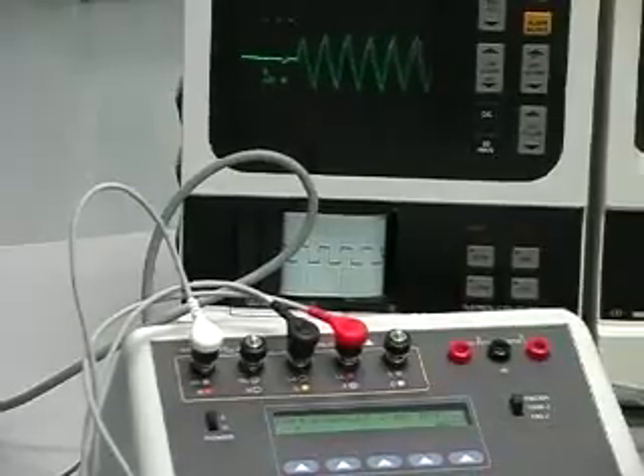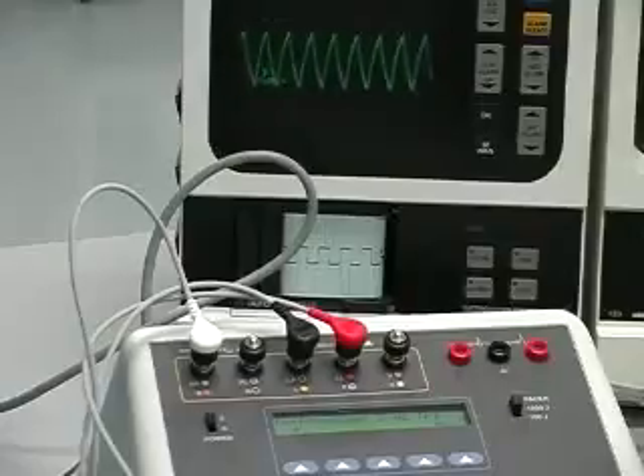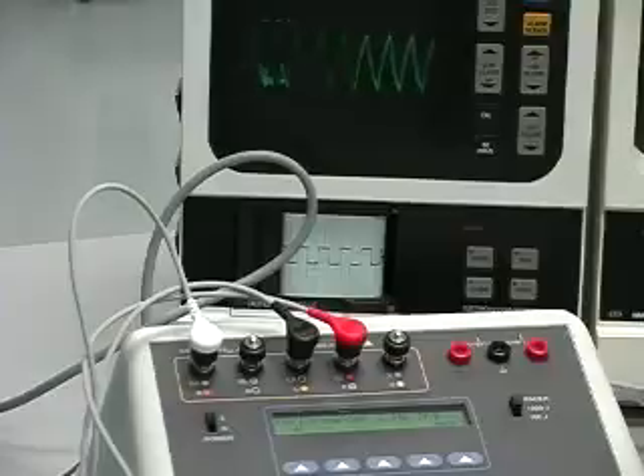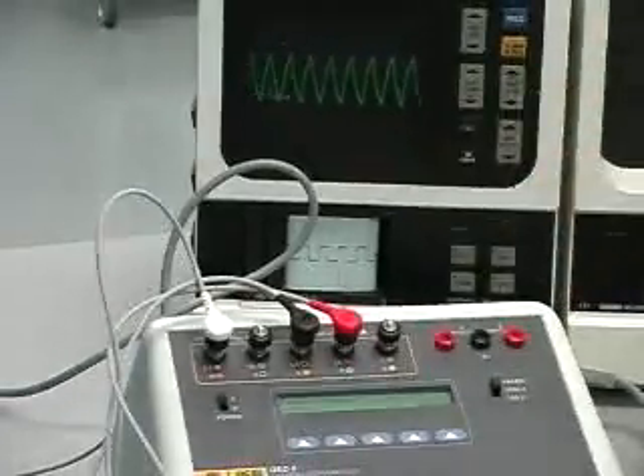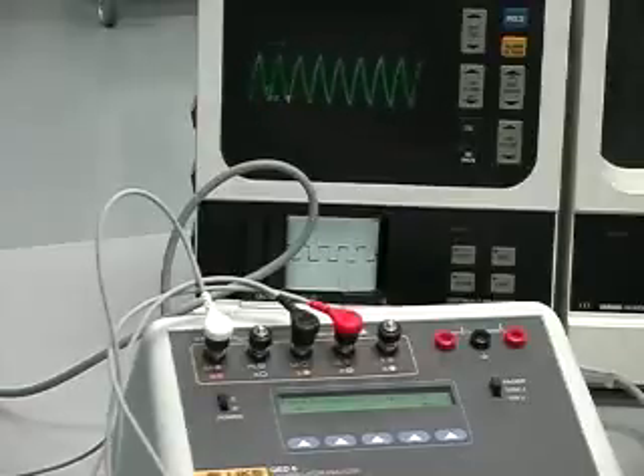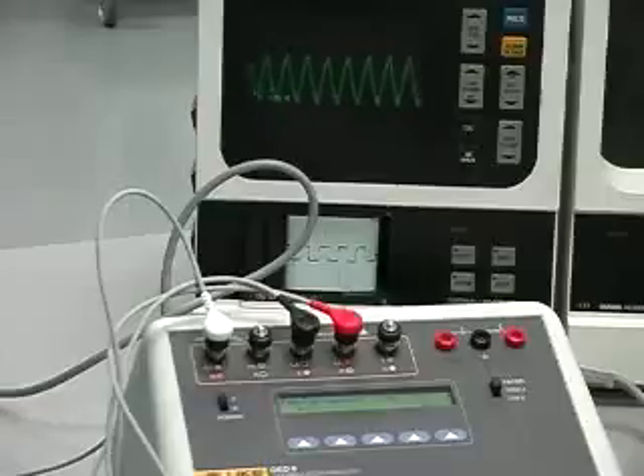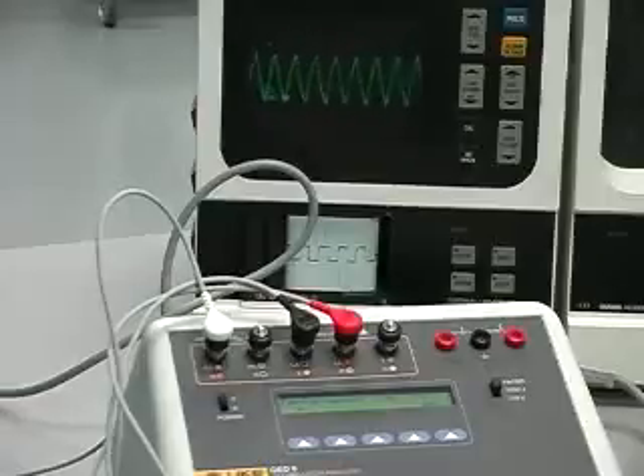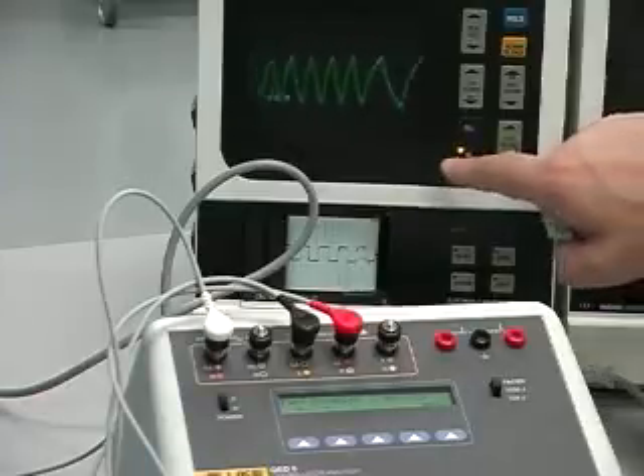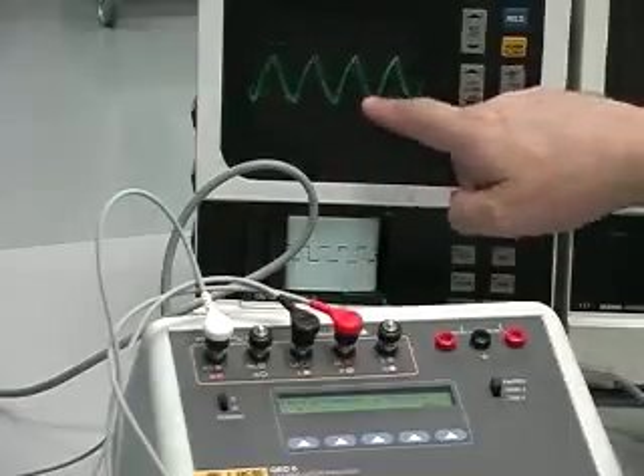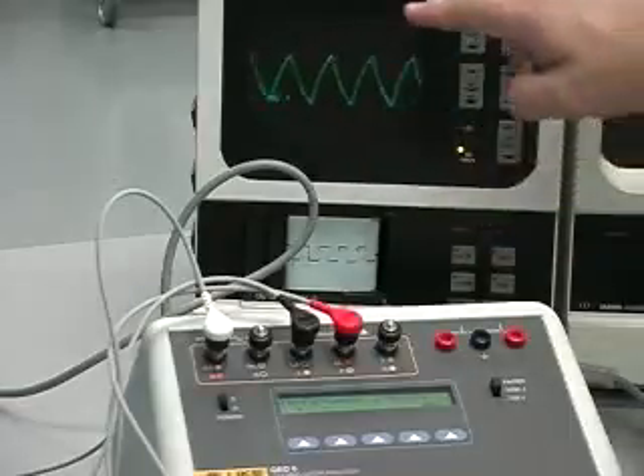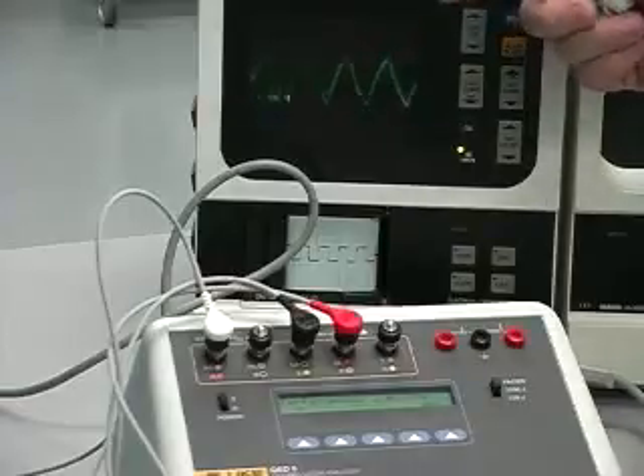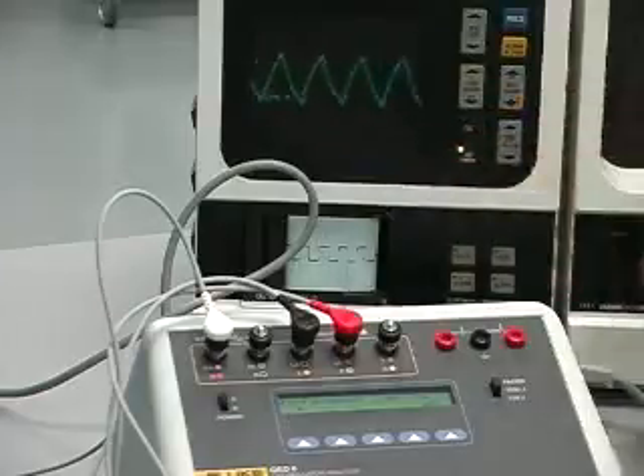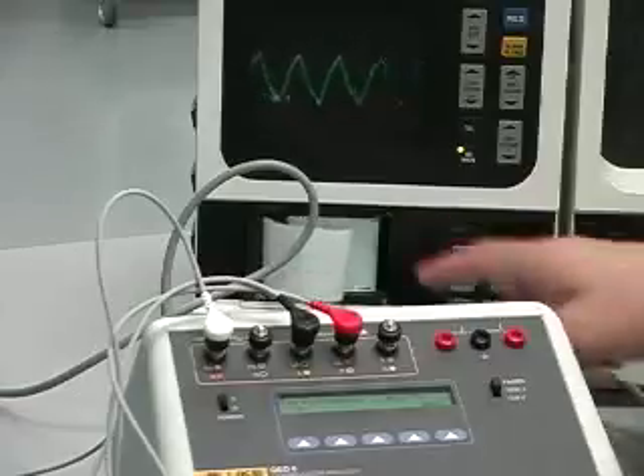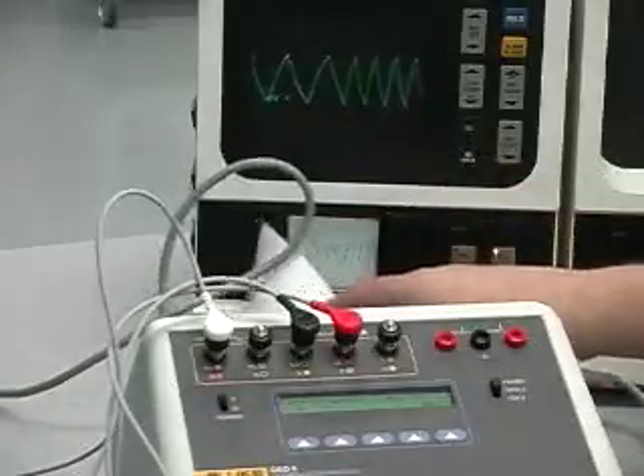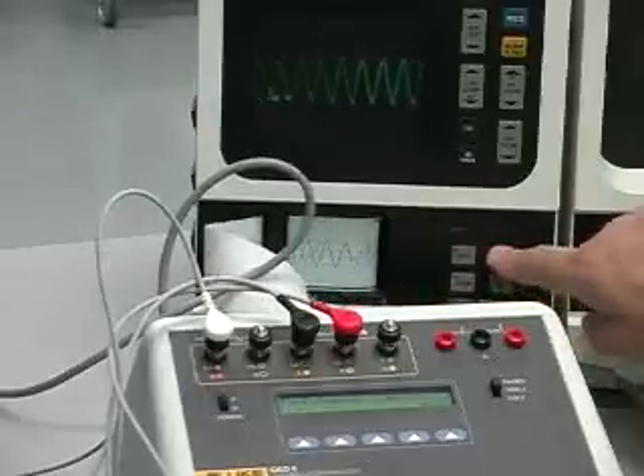2 hertz triangle wave, nice waveform for checking the linearity of your recorders and your monitors. Also, with the waveform, if you have any notching, if you're losing any of your least significant or even some of your most significant bits in your A to D converter, this is a real good way to find it out. This is an 8-bit waveform, so you see a little bit of notching just simply from the conversion within the monitor itself, but there's no major gashes or breaks in the waveform. And you're getting a good trace. I'm also using up all your paper.